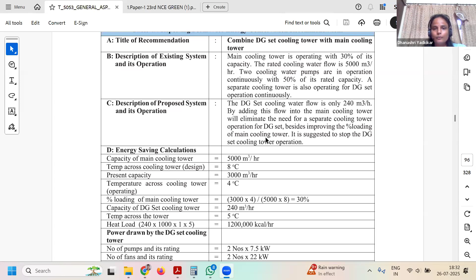The capacity of the main cooling tower is 5,000 meter cube per hour, and the temperature across the cooling tower, design value, is 8 degrees centigrade. The present capacity is 3,000 meter cube per hour, and the operating temperature across the cooling tower is 4 degrees centigrade. So the percentage loading of the main cooling tower is 3,000 into 4, present capacity, divided by 5,000 into 8, which is 30%. It's already given, so you need not calculate it again.